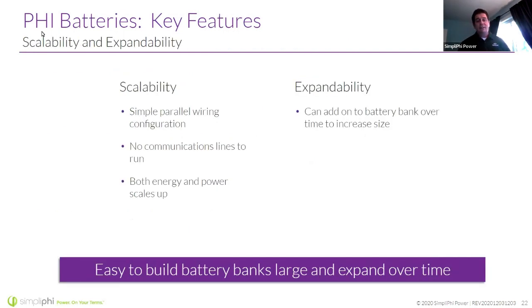Another key feature of our batteries is scalability and expandability. You may be used to home lithium-ion batteries available only in a 13.5 kilowatt hour chunk, where you buy and stack them in that size with no nuance. Ours, though, are 3.8 kilowatt hours, a much smaller building block, giving you more flexibility on system size. Maybe a customer really needs about 16 or 17 kilowatt hours, so 13.5 won't do it, and 27 would overdo it. With our battery, you can get to that energy level with more scalability.